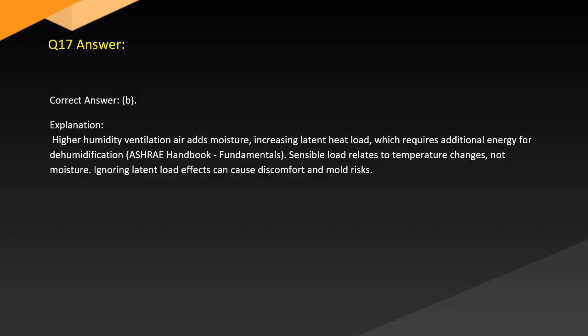Answer. Correct answer, B. Explanation. High humidity ventilation air adds moisture, increasing latent heat load, which requires additional energy for dehumidification. ASHRAE Handbook, Fundamentals: sensible load relates to temperature changes, not moisture. Ignoring latent load effects can cause discomfort and mold risks.